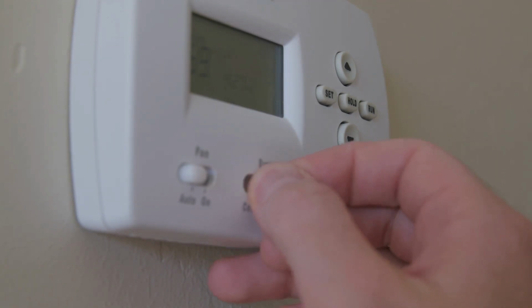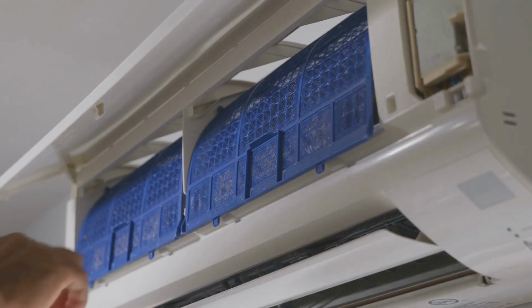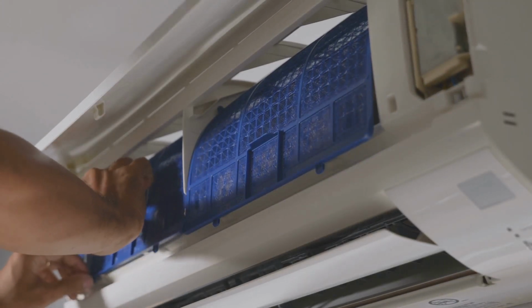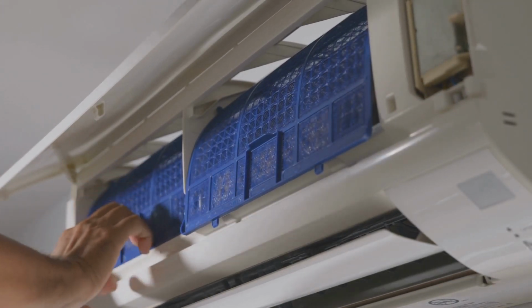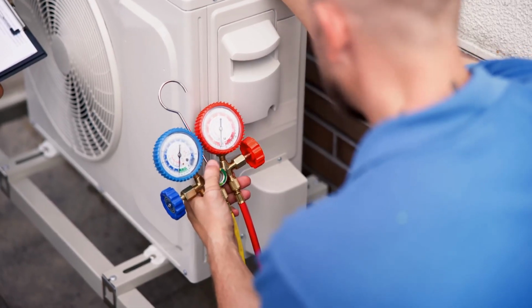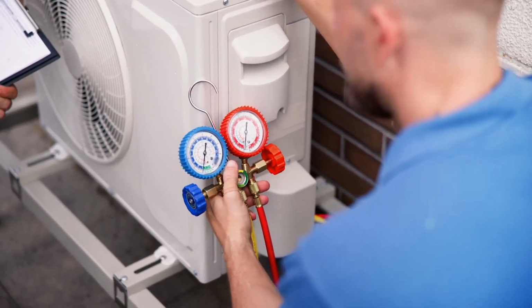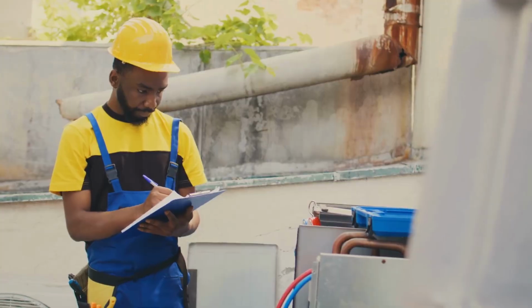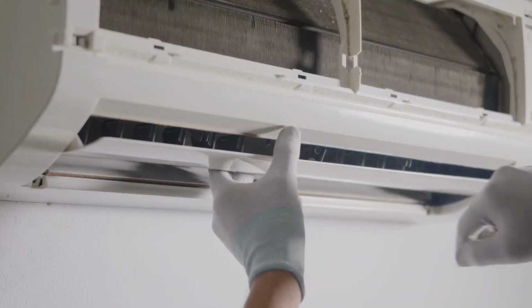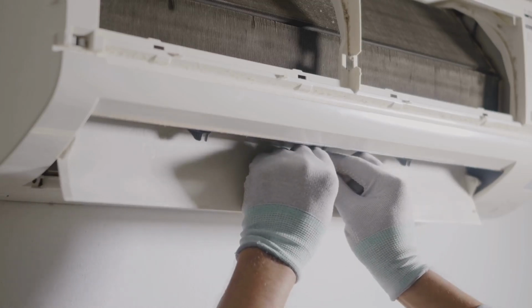Next, insufficient cooling. Make sure the air filter is clean and that there are no obstructions blocking the airflow to the indoor and outdoor units. If needed, check the refrigerant levels and contact a qualified technician. Another issue is water leaks. Inspect the condensate drain line for any clogs or kinks. Also ensure the drain pan is properly installed and not overflowing.